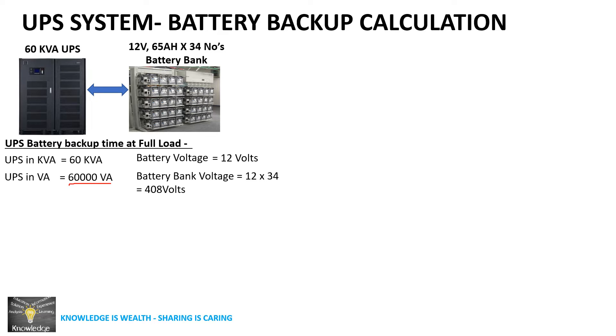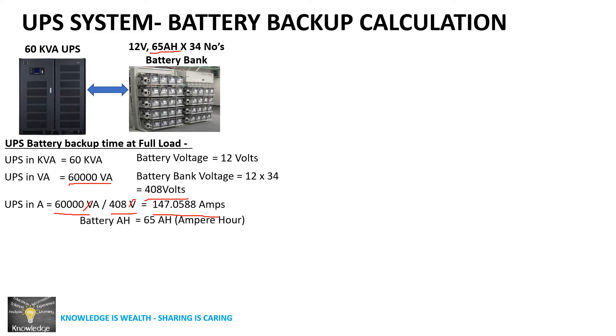Now we have the UPS capacity in volt-ampere and the battery bank voltage. To calculate the amperes: 60,000 volt-ampere divided by 408 volts — the volt units cancel — giving 147 amperes. The battery backup calculation is ampere-hours divided by amperes, so the ampere units cancel and we're left with hours.